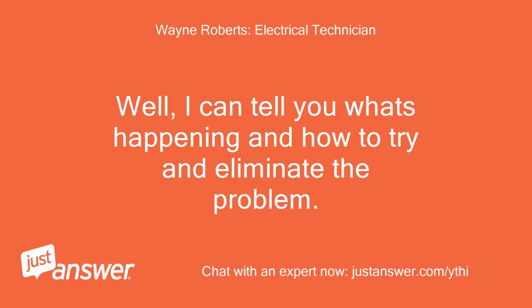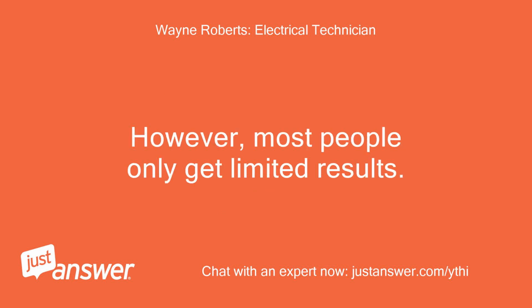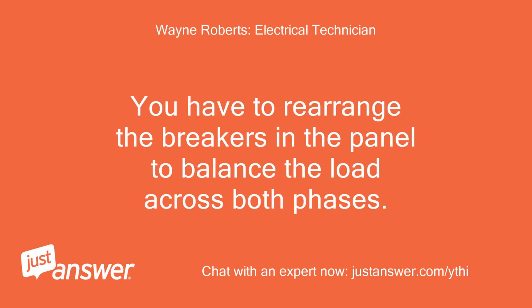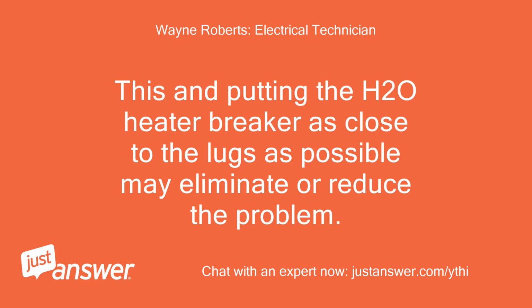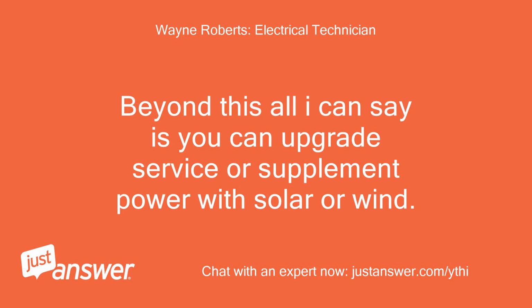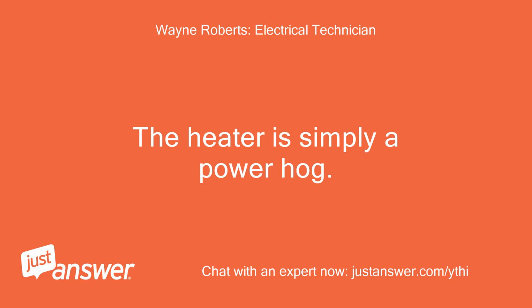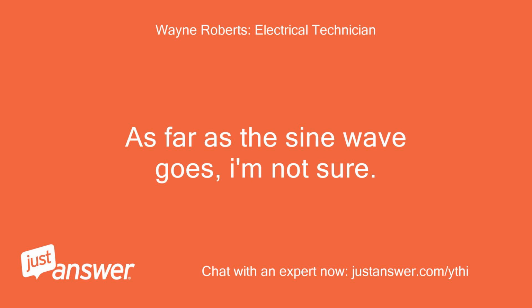Well, I can tell you what's happening and how to try and eliminate the problem. However, most people only get limited results. You have to rearrange the breakers in the panel to balance the load across both phases. This and putting the H2O heater breaker as close to the lugs as possible may eliminate or reduce the problem. Beyond this, all I can say is you can upgrade service or supplement power with solar or wind. The heater is simply a power hog. As far as the sine wave goes, I'm not sure.